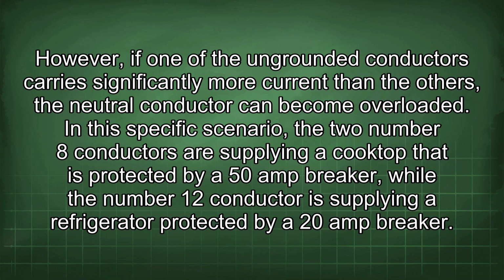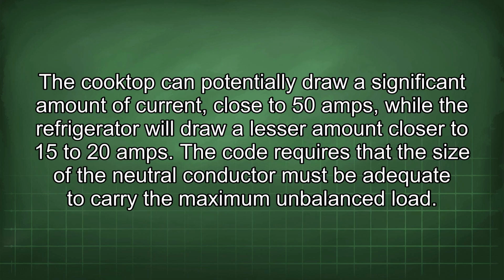become overloaded. In this specific scenario, the two number 8 conductors are supplying a cooktop that is protected by a 50-amp breaker, while the number 12 conductor is supplying a refrigerator protected by a 20-amp breaker. The cooktop can potentially draw a significant amount of current, close to 50 amps, while the refrigerator will draw a lesser amount, closer to 15 to 20 amps.